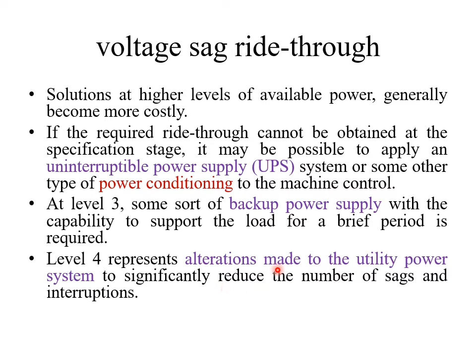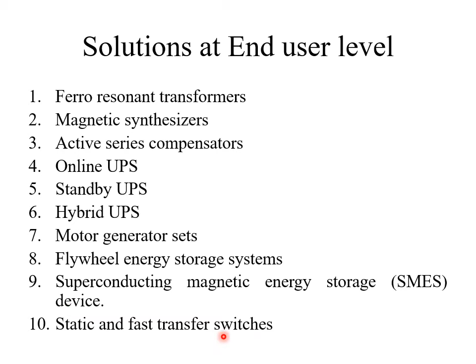So if the solutions cannot be done at the manufacturer level, then the best thing is that the solution should be done at the end user level. So at the end user level, what are the solutions that are available? The solutions are: ferro-resonant transformers and magnetic synthesizers, active series compensators, usage of UPS like online, standby, and hybrid UPS, then motor generator sets, then flywheel energy storage systems, then SMES, that is superconducting magnetic energy storage system, then static and fast transfer switches.